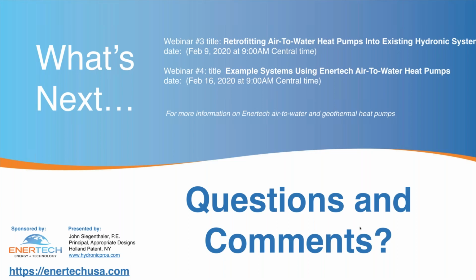Okay, and then the last question is, well, we've got some time for a couple more. What are some of the factors to consider when coupling the domestic hot water with an Enertech unit? Well, one of the things that's really nice about the Enertech unit, it has a domestic water mode. So there is a sensor that goes into that indirect tank that provides feedback to the heat pump, and the heat pump can start up and operate in, for example, a domestic water priority mode.